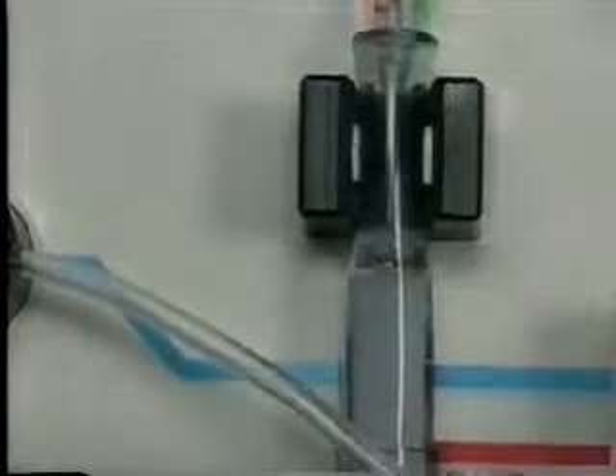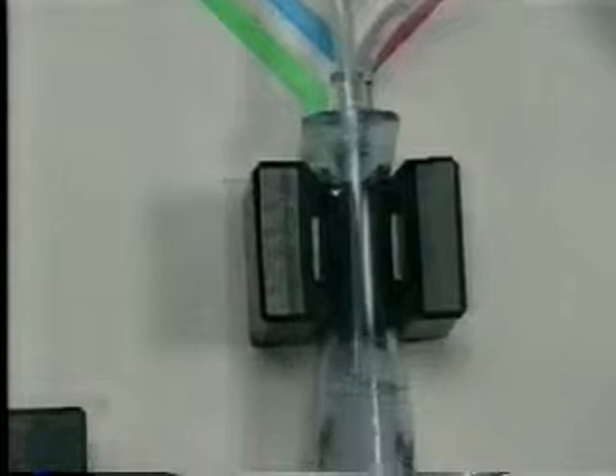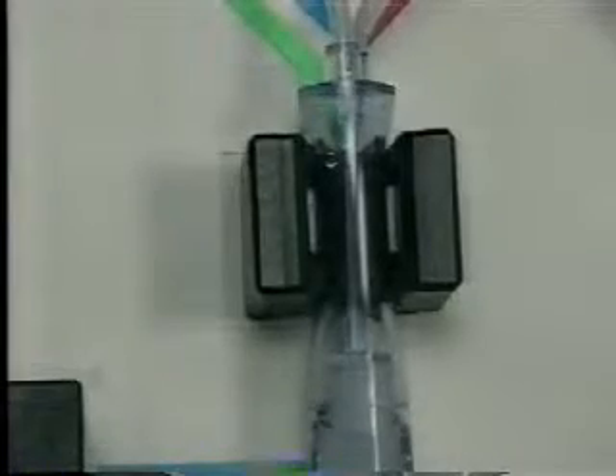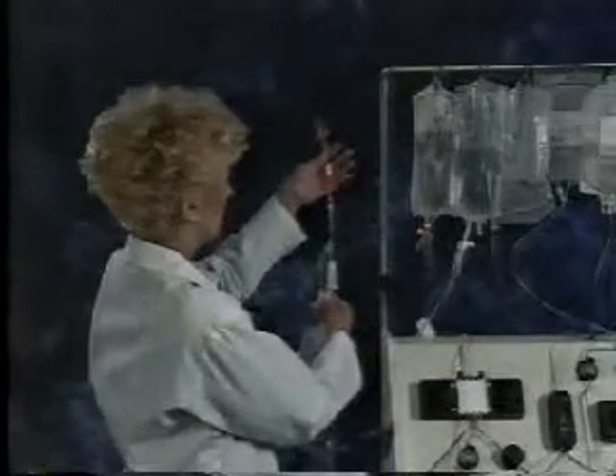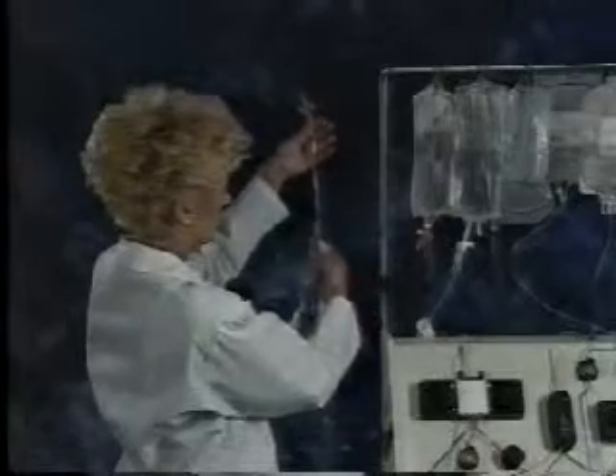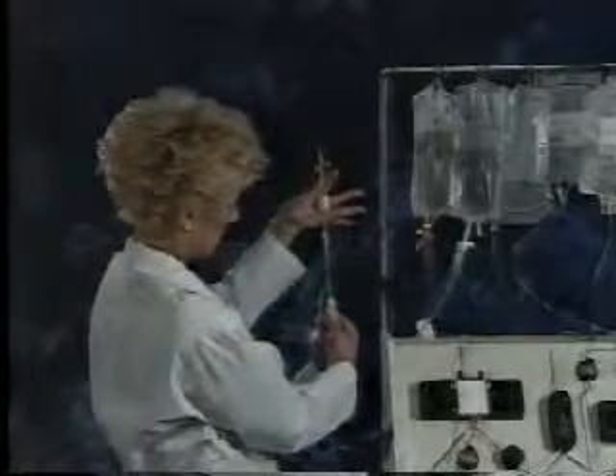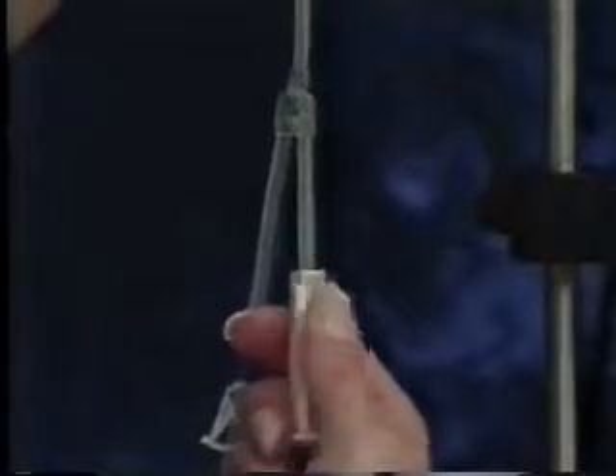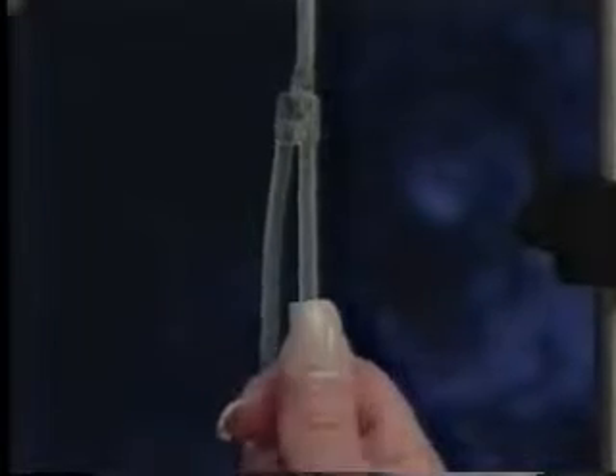The system will perform several tests as part of priming the tubing set. The valves will change position and the pumps will change flow rates as the Spectra system goes through the priming process. The display will show various messages to inform you of the progress of the prime. When the system instructs you to prime between the Y manifolds, open the white pinch clamp on the needle line. Hold the Y manifold slightly below the level of the saline bag.